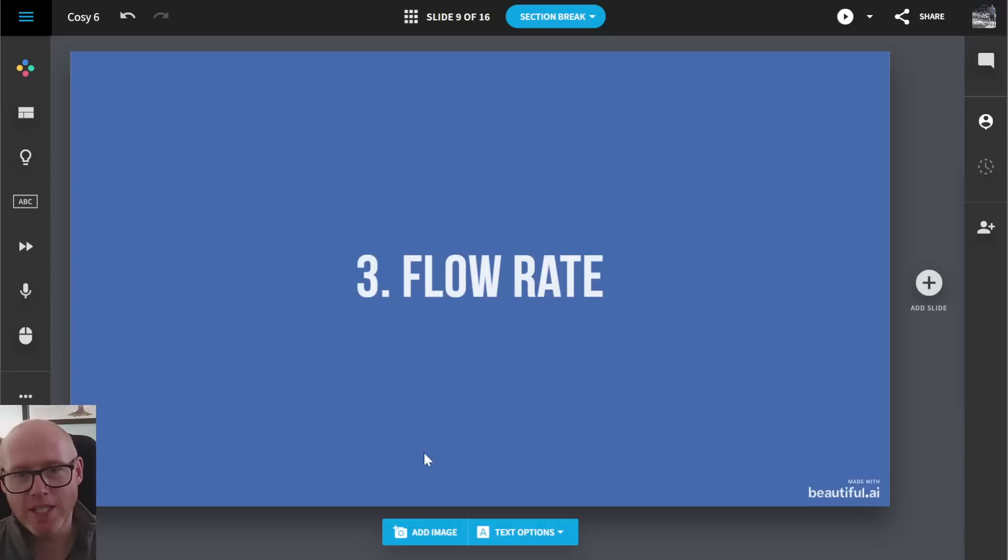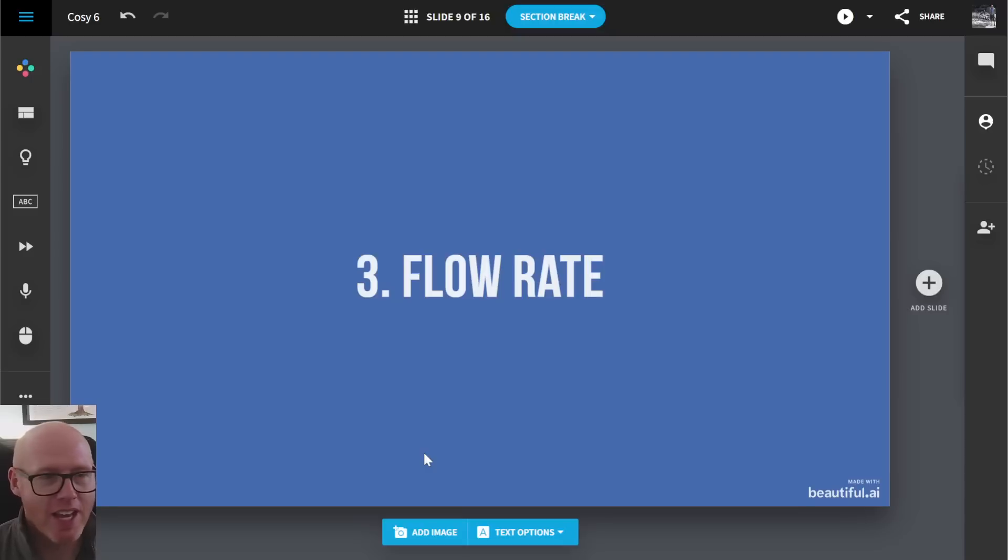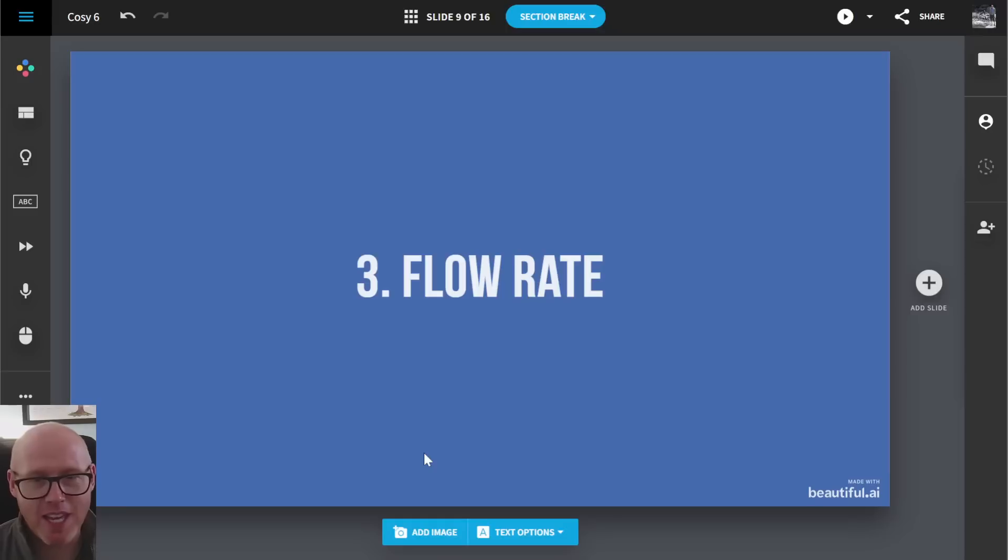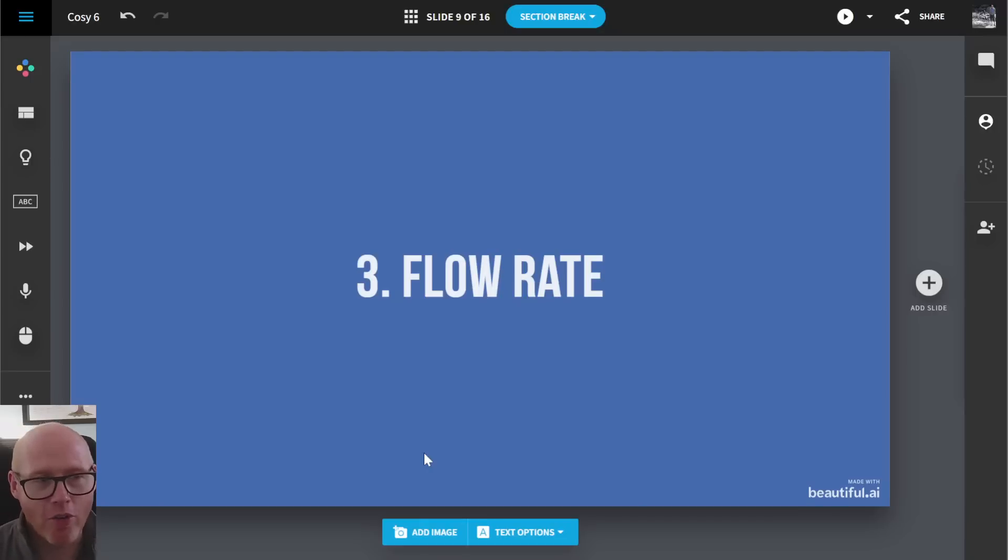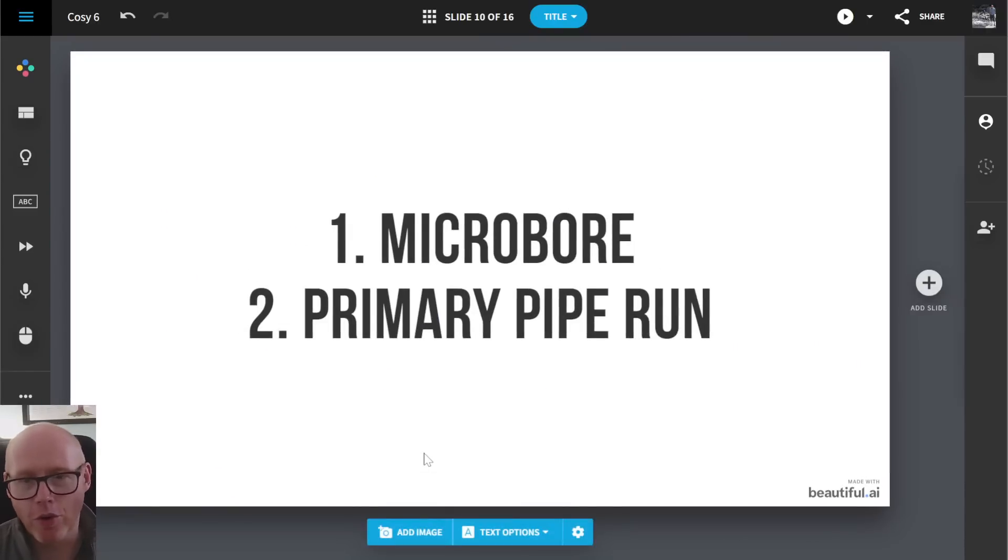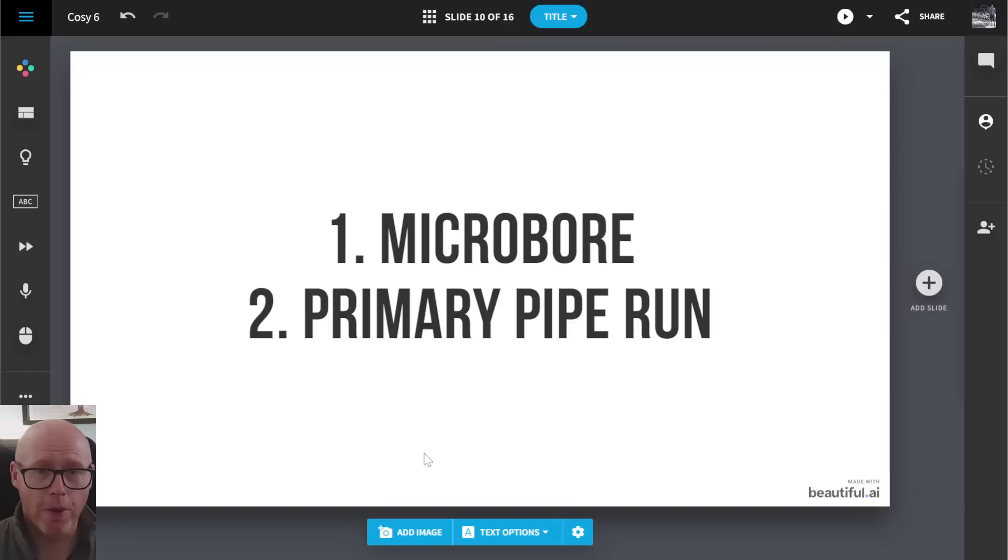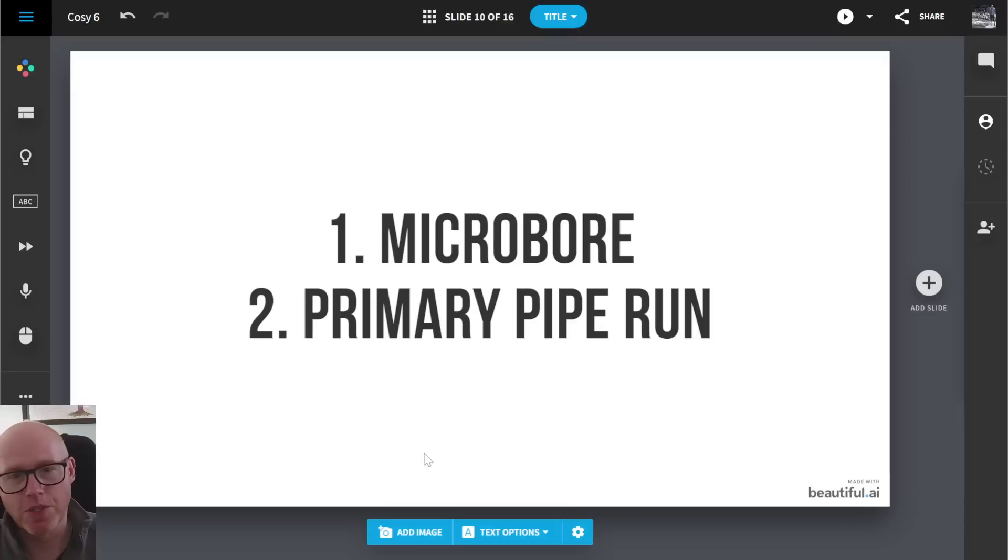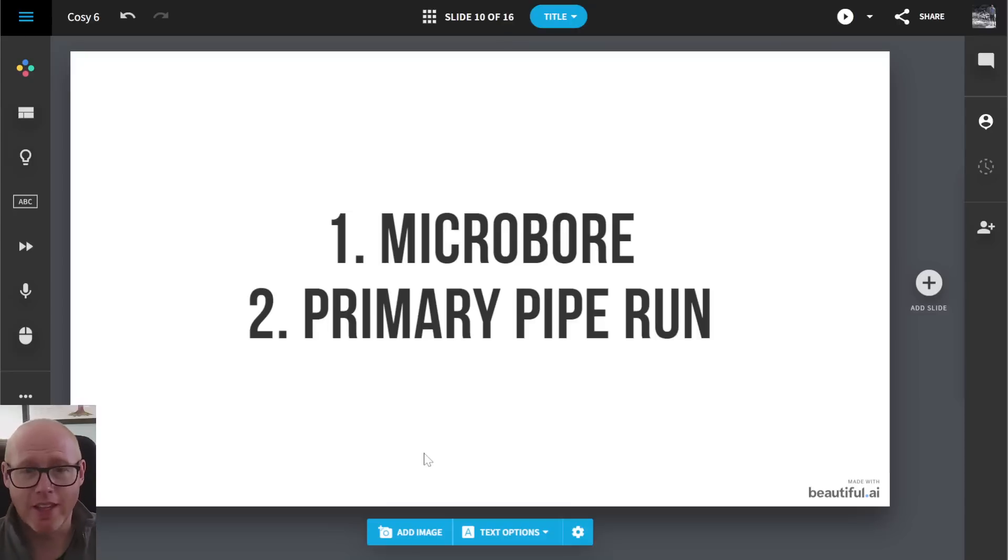Well, you've got 10 millimeter plastic micro bore. You need to really be doing your calculations. And secondary to that, I don't know how many meters of external pipe work he's got. But it looks like a good 25, 30 meters, maybe even more than that. That's quite a lot of external pipe work. Not necessarily the end of the world. I'd love to see how well insulated it is and get a thermal imaging camera on that. See how much energy he's losing through that long run of pipe work. The pump inside the Cozy 6 should be plenty enough for a long primary pipe run. But to overcome such a long pipe run and then micro bore pipe work throughout the house, I don't know the extent of it. I don't know if it's just 10 millimeter tails to the radiators, if it's just drops. I don't know if he's got main system, like 22 mil primaries running through the property and then the 10 mils branch off. We don't know. We don't know any of that.